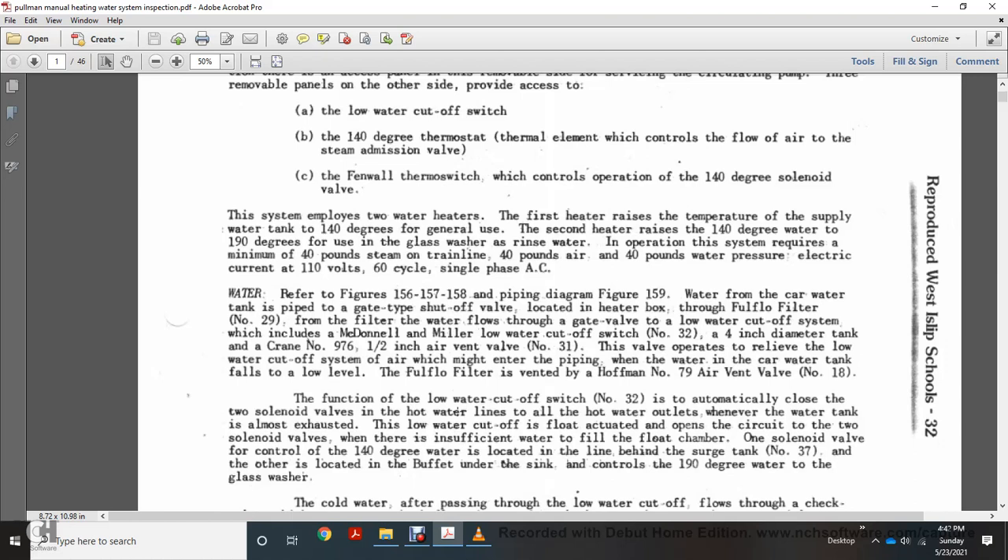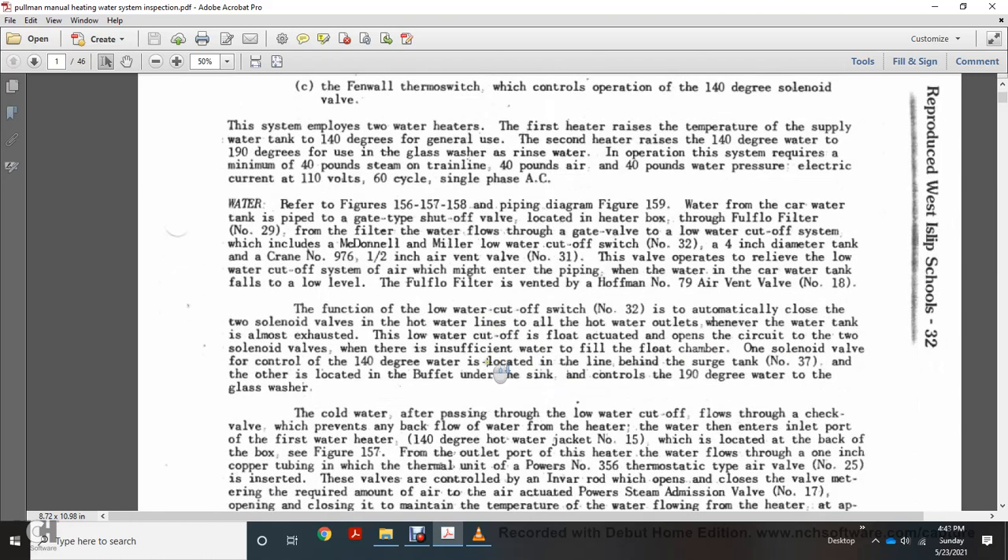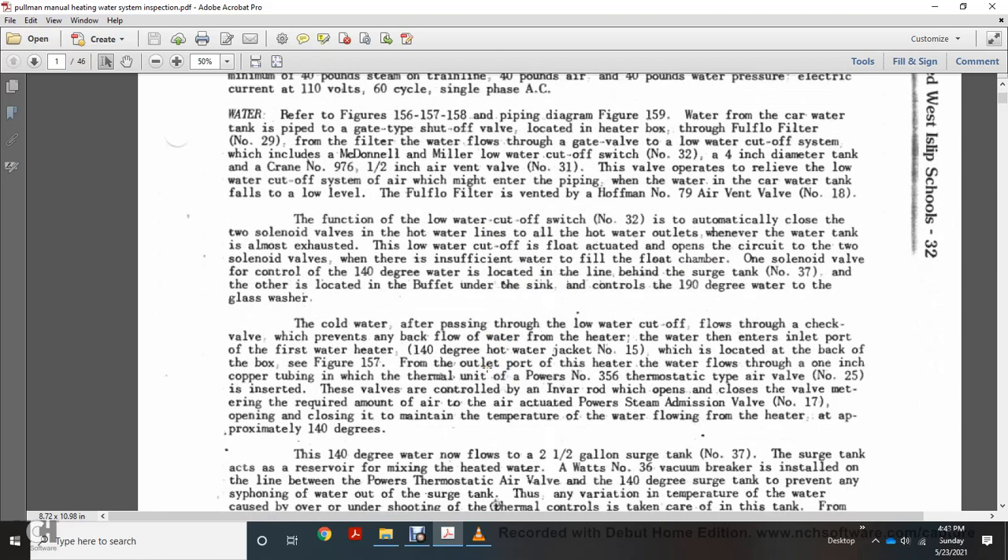Referring to figures 156, 157, 158, and piping diagram figure 159: water enters the car water tank through a gate-type shutoff valve located in the heater box, through filter number 29, through the gate valve of the low water cutoff system, which includes the McDonnell and Miller low water cutoff switch number 32, a 4 inch diameter tank, crane number 976 half-inch air vent valve number 31. This valve operates to relieve air that may enter the piping when the car water tank falls below the lower level. The water filter is vented with Hoffman number 79 air vent valve number 18.